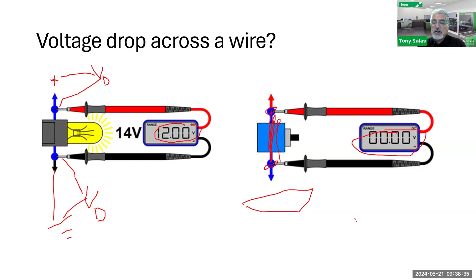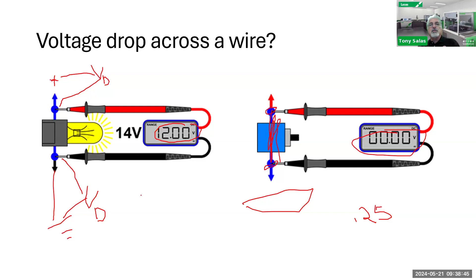So if this circuit breaker has been reset a whole bunch of times and it's starting to wear and tear, yeah, it's going to show a voltage drop, but it should not exceed more than 0.25. That's what you want to see. Y'all follow me? Hopefully that makes my point, because we're trying to make sure that the circuit is working correctly.